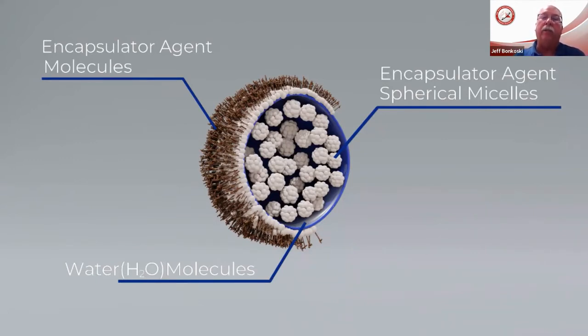The other thing is when we look at Class D metals, when we look at some of these other fires where you end up with an explosion because of the reaction with water, you have to understand now we've put that skin on the surface of the water droplet. So by doing that, it's now no longer the water that's coming in contact with those Class D metals. We put that skin on there, so we're able to rapidly start cooling and being able to extinguish. And because we've changed that mechanism of cooling, okay, we no longer have to worry about steam.